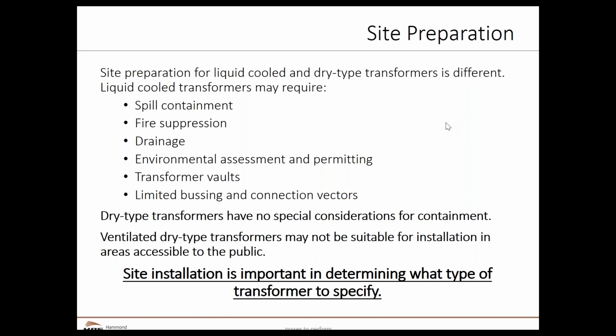If you want to get the best value out of a dry type versus a liquid filled, you really have to compare the application, and you have to come up with a dry type specification and site preparation work specific to that dry type transformer to get the true value out of it. If you're looking just at the cost of the two transformers and not including some of these additional preparation costs, a lot of times it'd be more favorable to a liquid filled transformer. When you take these other issues into consideration, that would adjust a lot of times where your cost and benefit analysis would bring you.